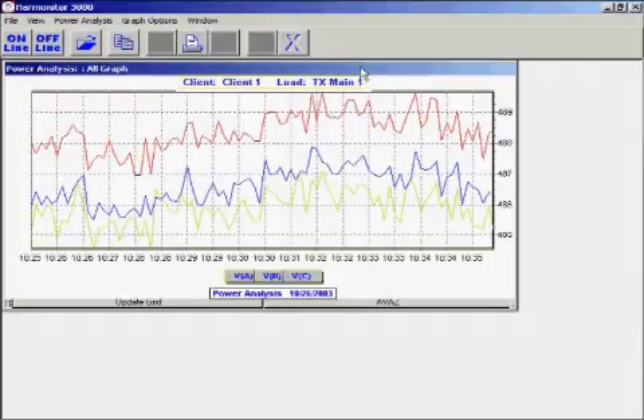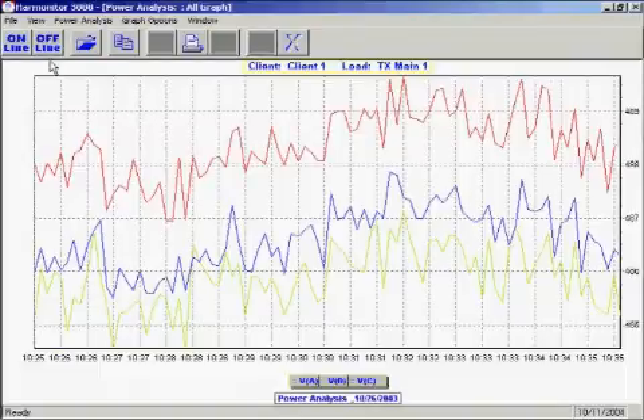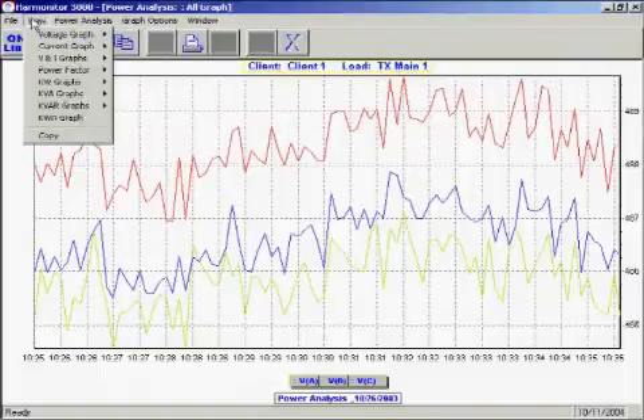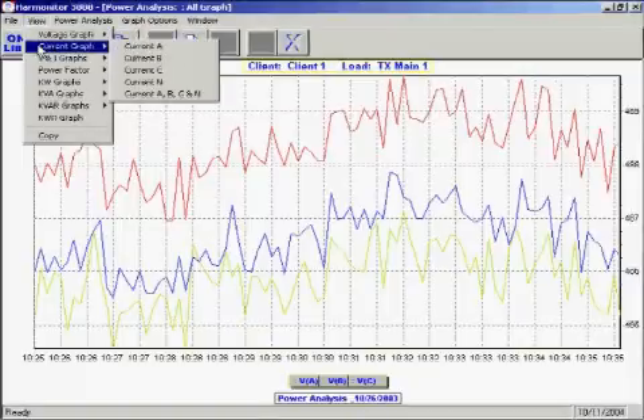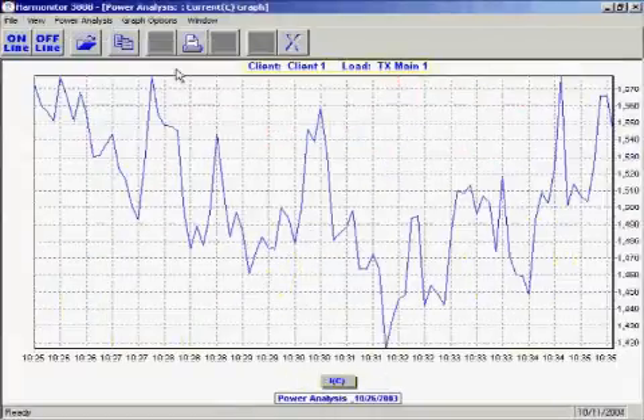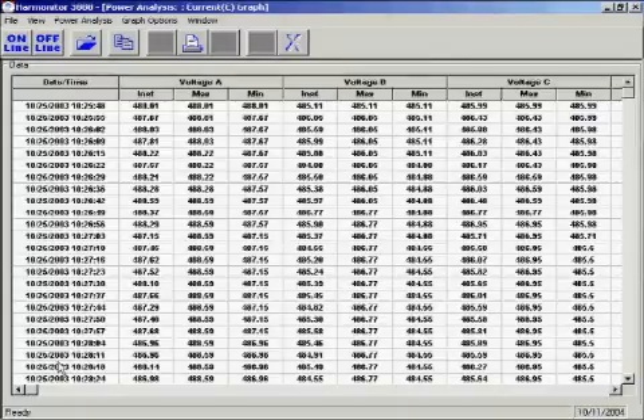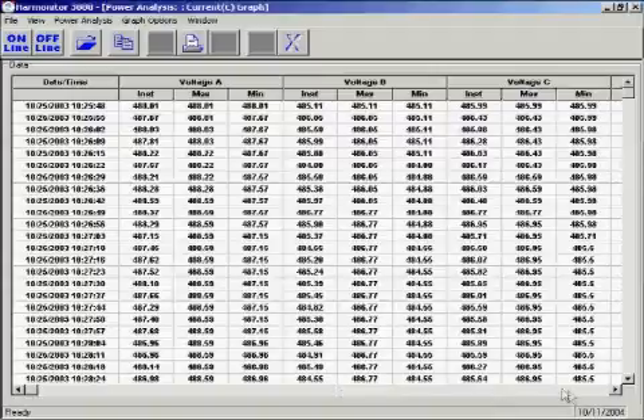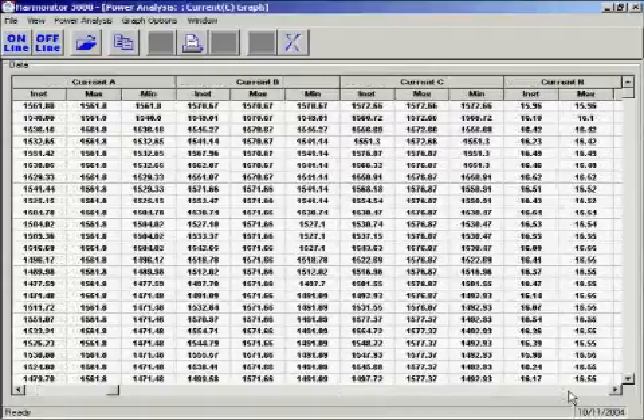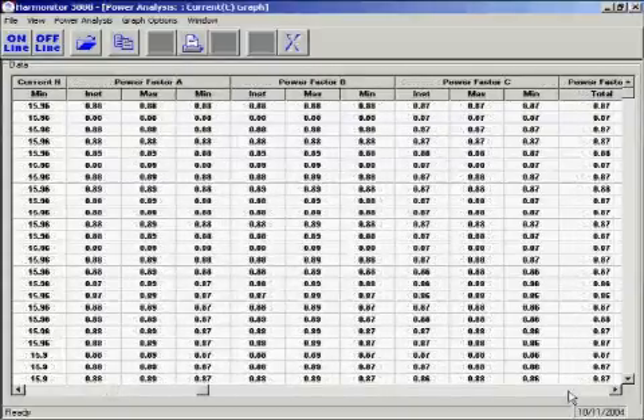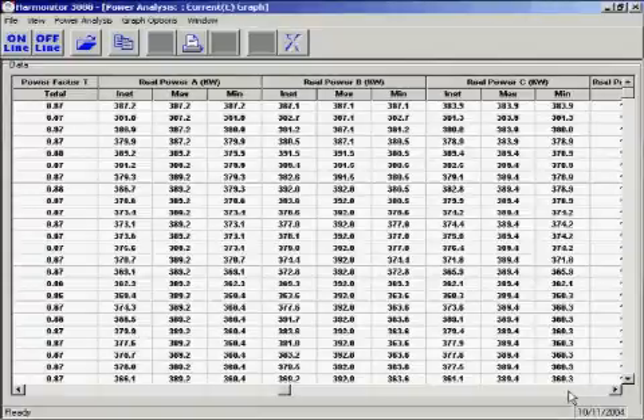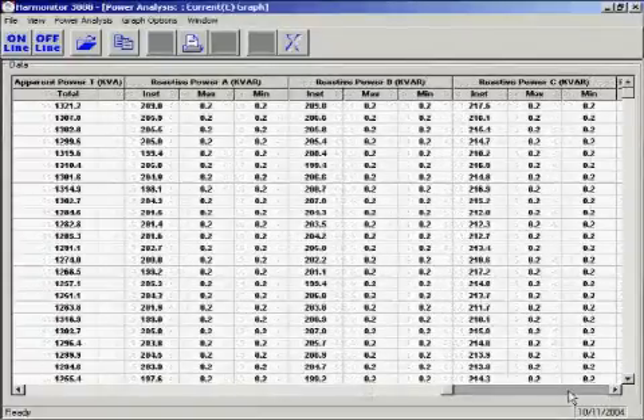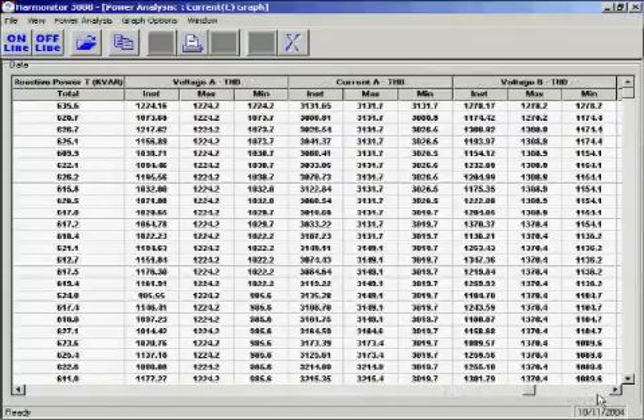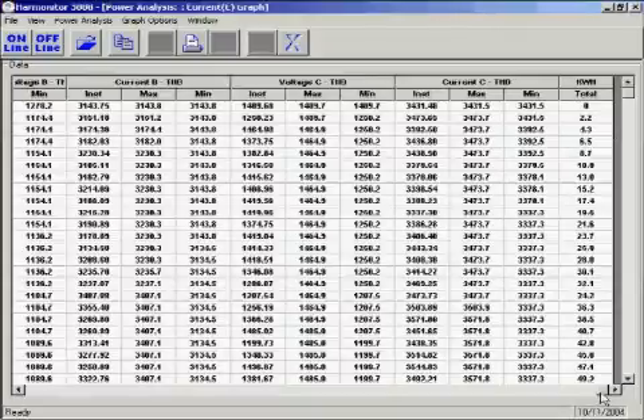The default graphical display is voltages for phases A, B, and C. To view other graphs, go to the View menu, select the type of graph you wish to view, and then select which phase you'd like to view. To see data in a tabular form, double-click on the graph. Here, the first column shows the date timestamp for each sample. Next, phase voltages, phase currents, power factors, real power, apparent power, reactive power, total harmonic distortion for both voltage and current, and finally kilowatt hour. To close this window, press the X button.